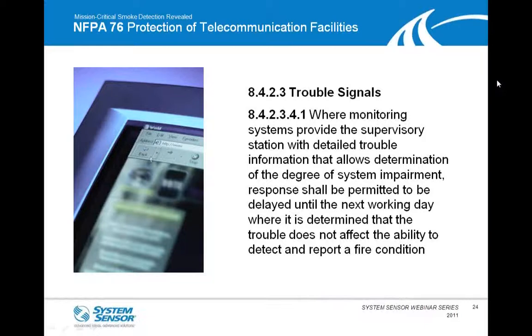And for this one, I'm just going to flat out read the standard here. It says where monitoring systems provide the supervisory station with detailed trouble information that allows determination of the degree of system impairment, response shall be permitted to be delayed until the next working day, where it is determined that the trouble does not affect the ability to detect and report a fire condition.